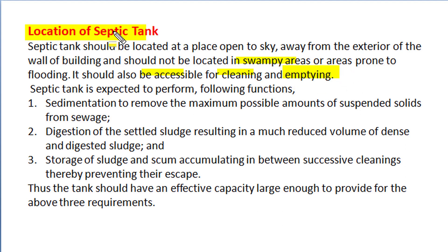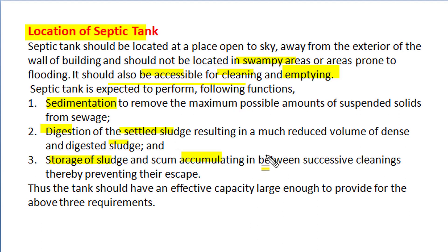In any household sewerage system, the septic tank is expected to perform three functions. First, sedimentation action — to remove the maximum possible amount of suspended solids from the sewage. Second, digestion action of settled sludge — resulting in much reduced volume of dense and digested sludge. And finally, storage of sludge and scum accumulating between successive cleaning or emptying actions, thereby preventing escape of sludge, scum and other pathogens associated with septage. Thus, the tank should have an effective capacity large enough to provide for all three functional requirements: sedimentation, digestion and storage of sludge and scum.